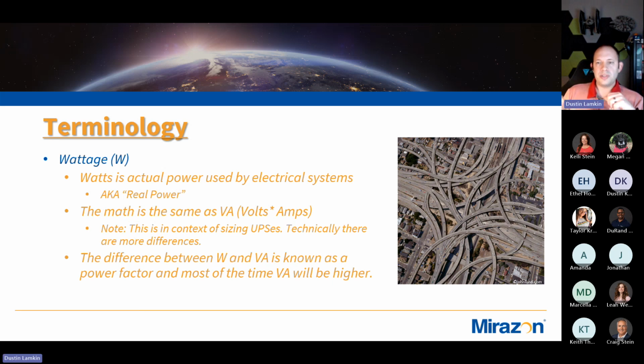So using that same math, we get wattage. While volt amp is what we use to size the circuits, the wiring, and the UPSs, wattage is what those systems actually pull. It seems like a small difference, but it makes a big difference once we're sizing it, because we don't want our volt amps to match our wattage — that means we've severely undersized our system. So we need to make sure that the volt amps is higher than the wattage we are planning on pulling.